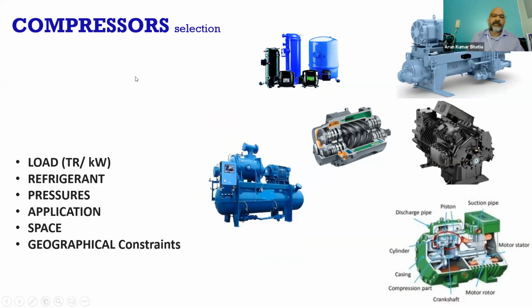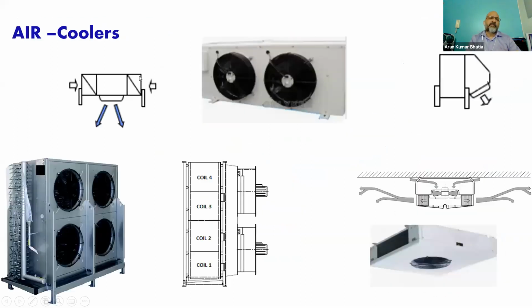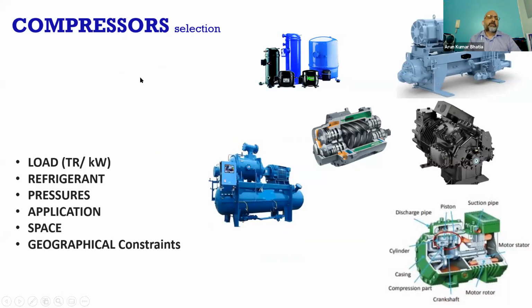Now let us understand from my perspective how important it is and how we can select the compressor. Earlier someone was asking about the refrigerant being in direct touch with the product. For compressor selection, the refrigerant is also very important, as is your load. For example, if you have a 50 kilowatt load or a 10-ton load, you can use a small scroll compressor, or for a 5-ton load, you can use a reciprocating or scroll compressor.